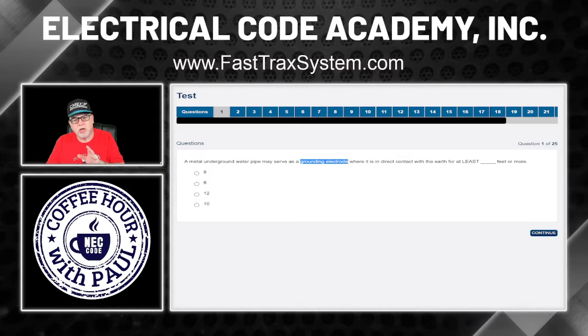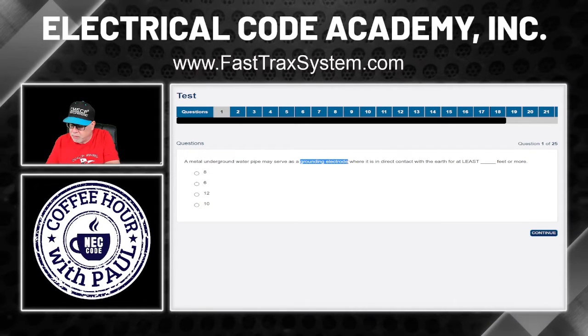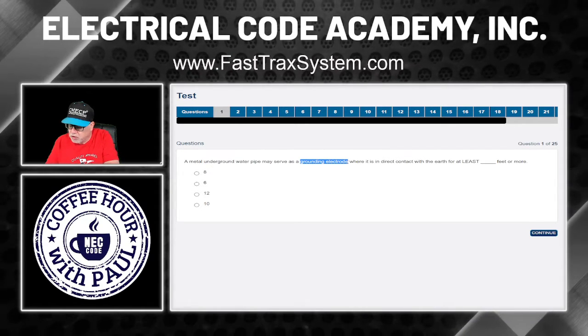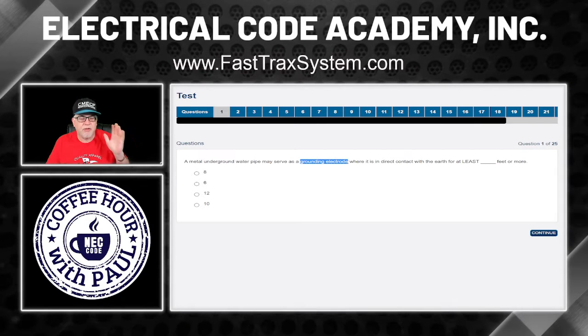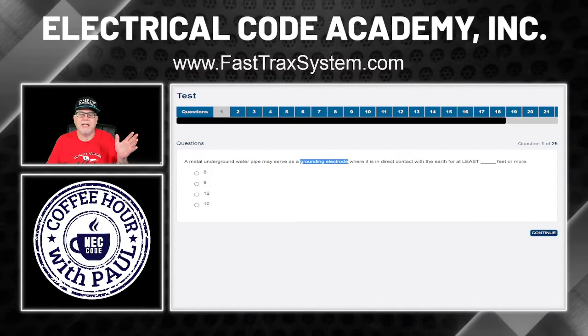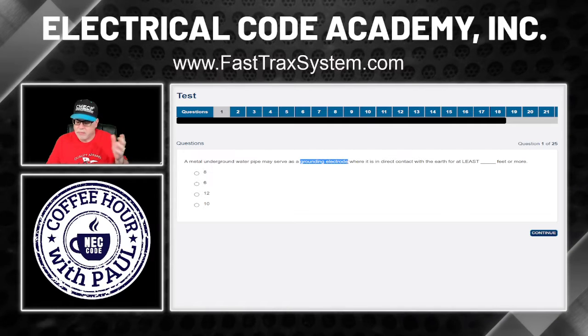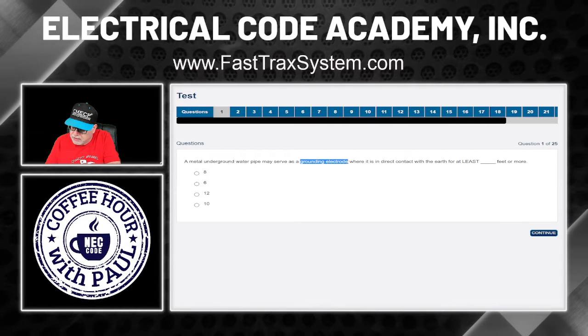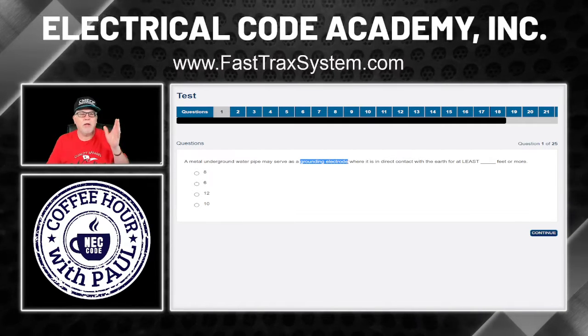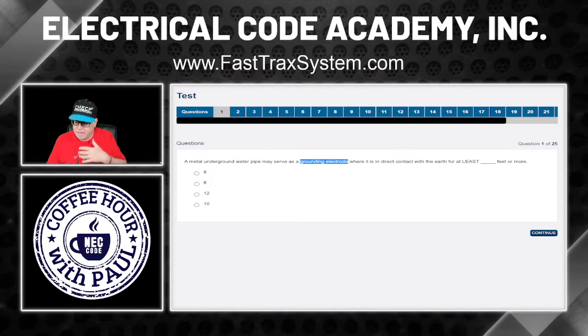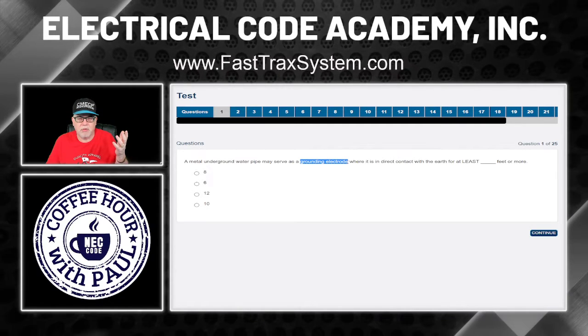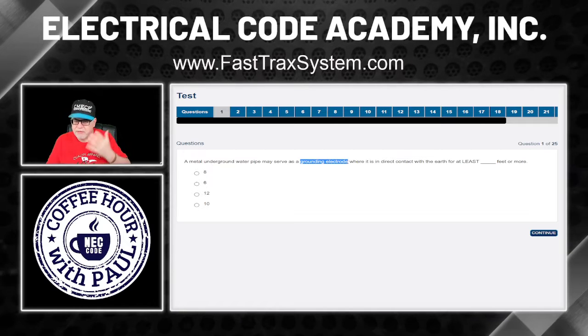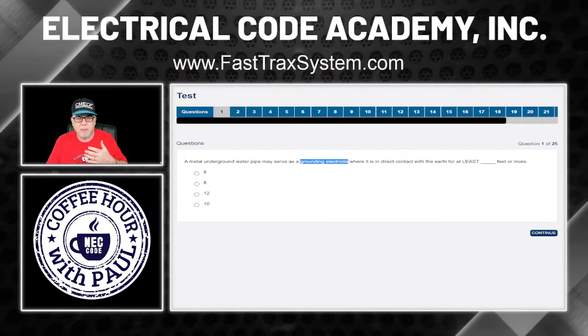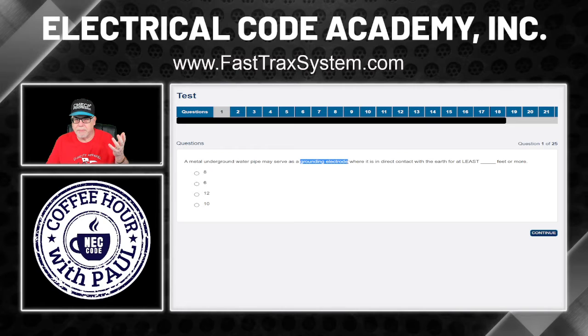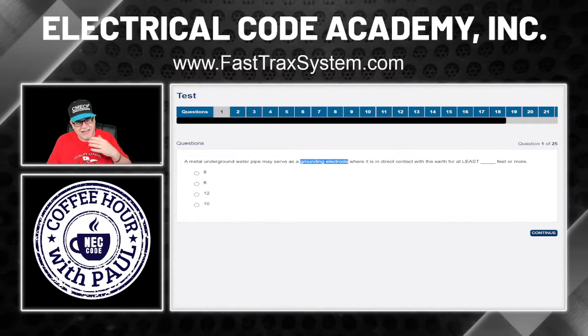Because what you're going to do is you're going to dissect this. Here it says metal water pipe. So you would have gone to 250.30 and looked at it, and you would have said, well, okay, I get it. That's separately derived system. Then you would have gone to 250.52, and you would have gone, hey, that's grounding electrode types, different list of ones. And A1 happens to be the water pipe type grounding electrode. So that's how you would do it.